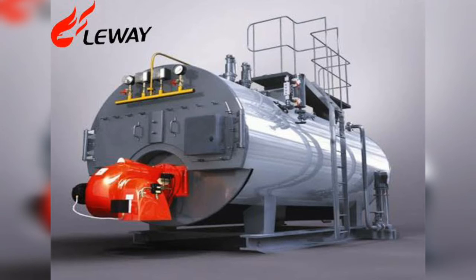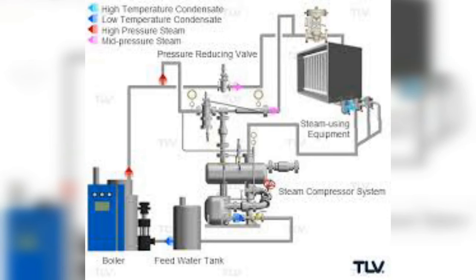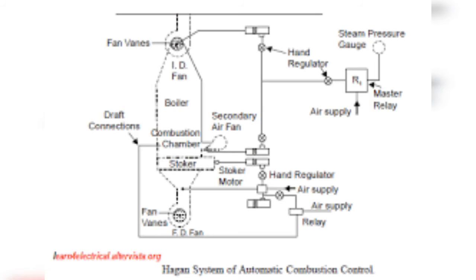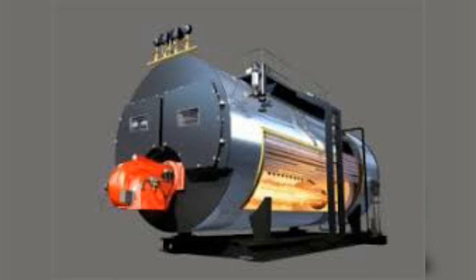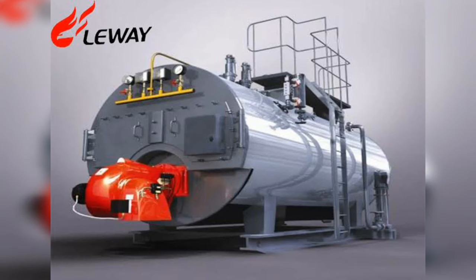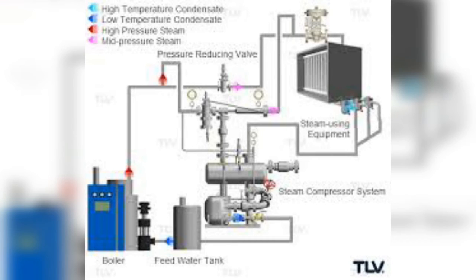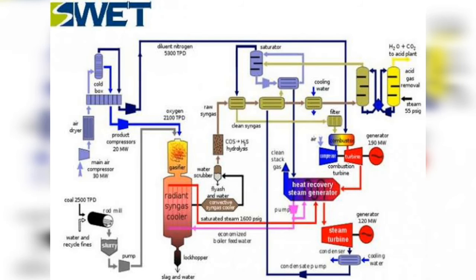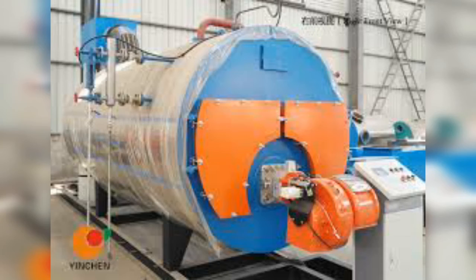Simultaneously, the secondary air fan damper gets opened proportionally. A readjustment of the induced draught takes place, stabilizing the condition in the combustion chamber. Relay R2 alters the position of the forced draught fan servo motor to adjust the position of the forced draught fan so that stable conditions in the combustion chamber are maintained.